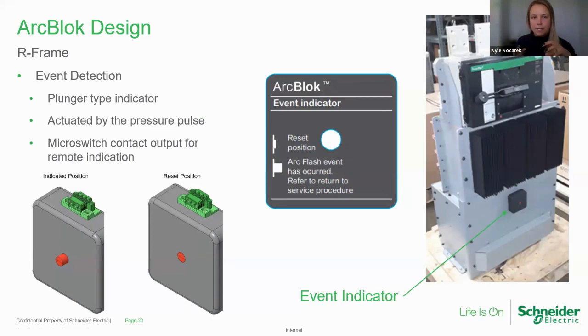All you might have is some surface pollution, like some carbon of whatever burned up on your cables. But we've tested some units at our Cedar Rapids lab where the engineers are for this, like 9-10 times. Schneider Legal, being who they are, we're able to claim ArcBlok is good for up to 5 events. A lot of people much smarter than me would argue with ArcBlok, you won't have an event on the line side because of those barriers and your isolated phases. But we're rating it up to 5.